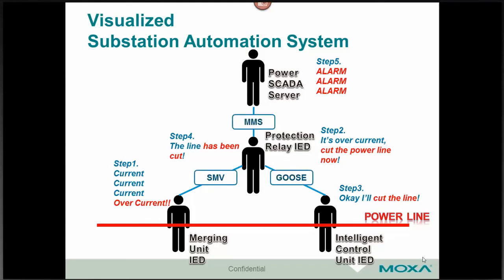Really, these are the protocols that are used within 61850. So your Sample Measured Value, or SMV, is what's happening between the merging unit and protection relay, using that particular protocol to report back to the IED.